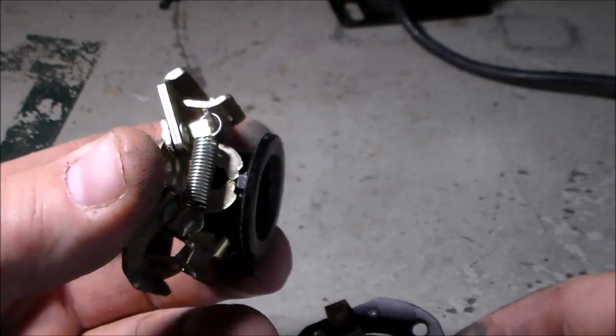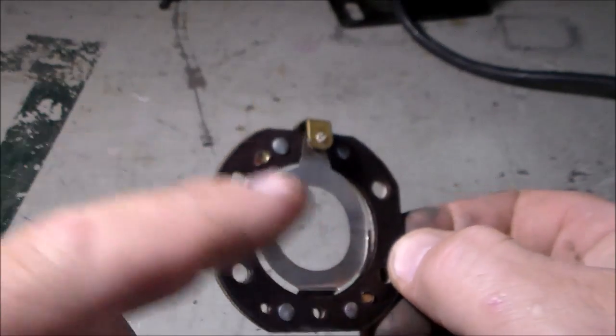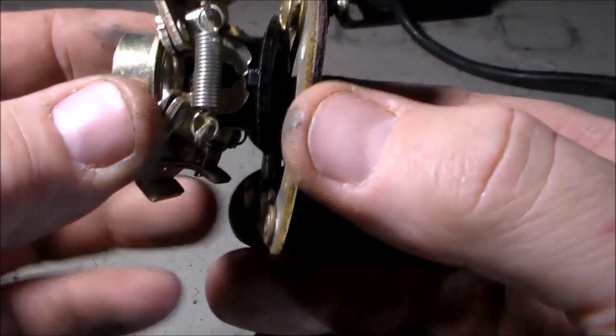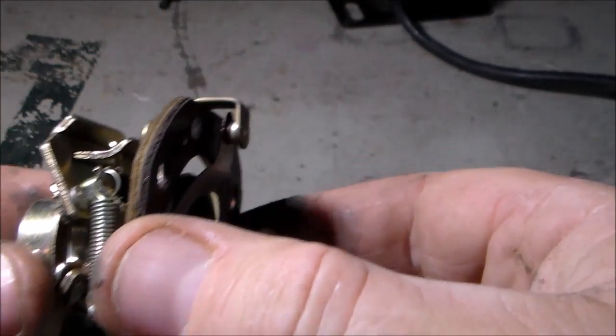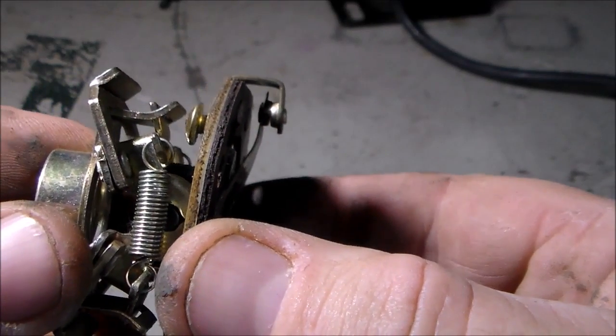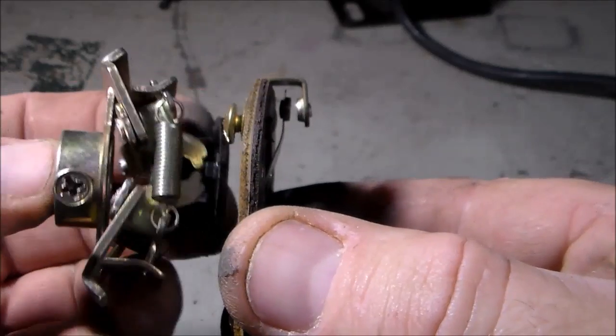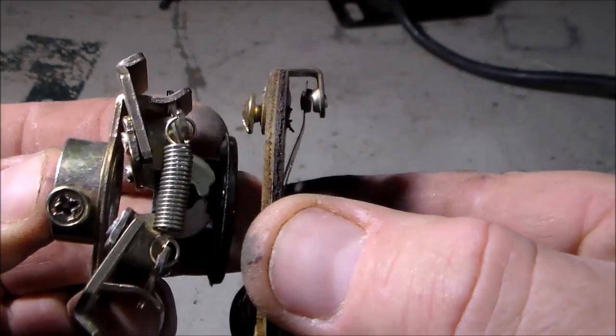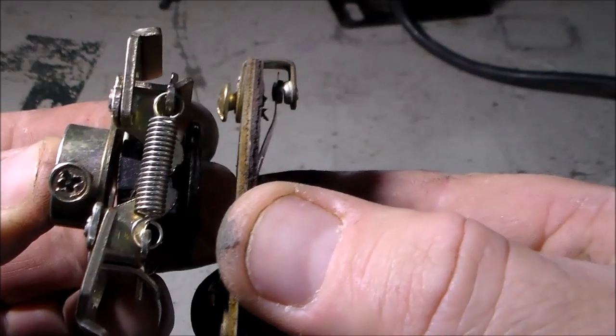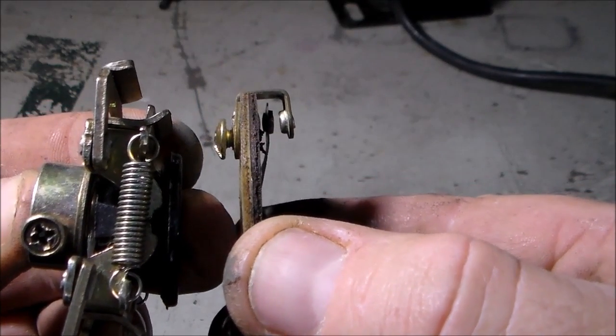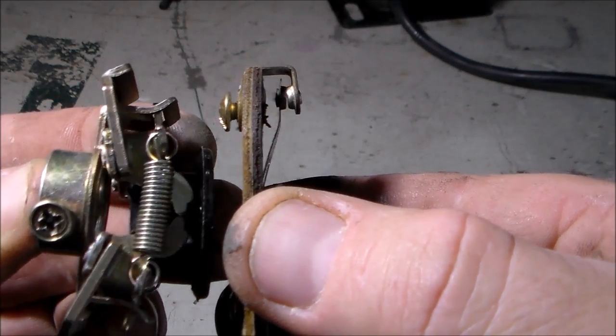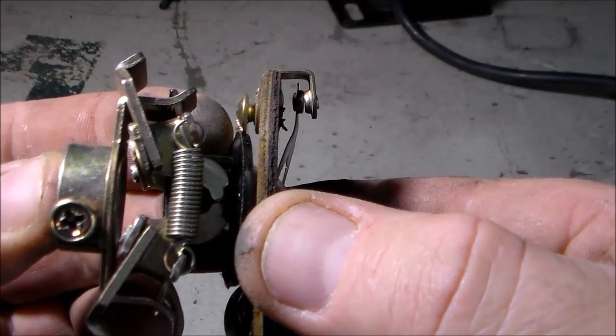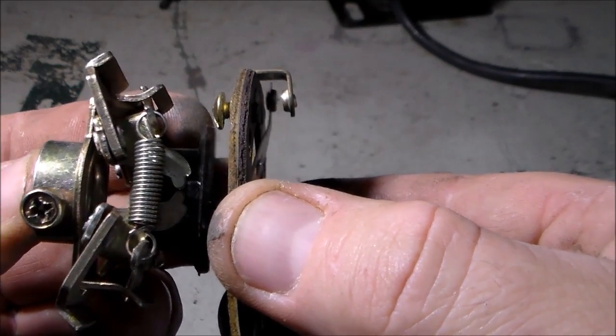This is the centrifugal part. The plastic rides on that, on this ring. And it keeps pressure on the contact, keeps it closed. And as this comes up to speed, the plastic piece pulls back and in turn releases that capacitor out of that start winding. When you turn it off and the speed slows, this starts to expand and pushes back on that contact so it's ready to start the next time.